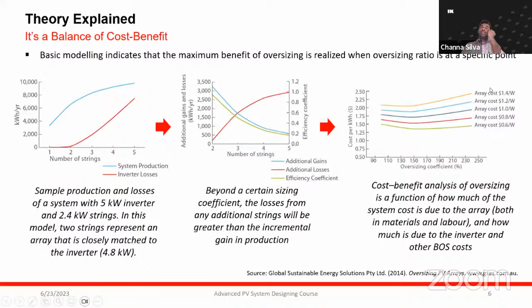So you can see that the oversizing, they are rated for 210, 250. So someone can think, is there a possibility to oversize by 250%? Some manufacturers just provide some specific range of products, but by looking at the solar irradiance as a factor, which can go beyond 1,000 watt per square meter, I never recommend going to that sort of extent. It is also financially not feasible, because in that particular range a huge amount of energy is being lost.